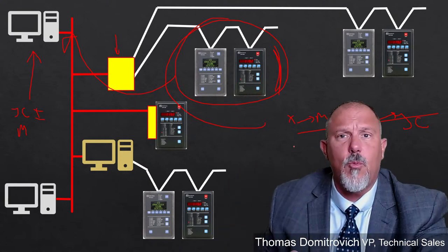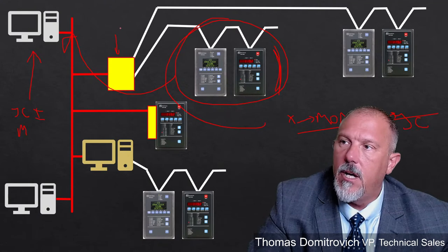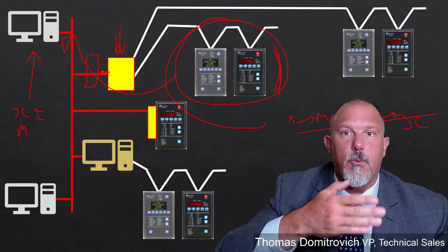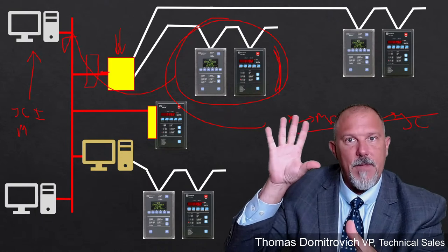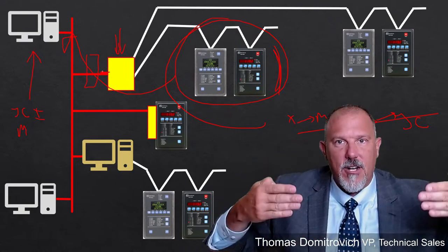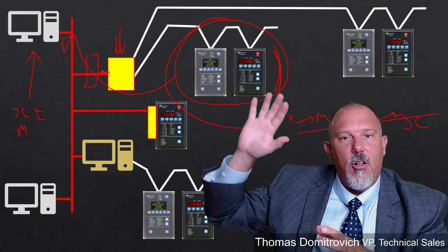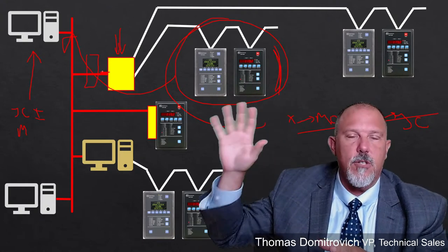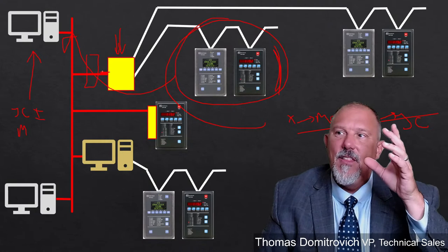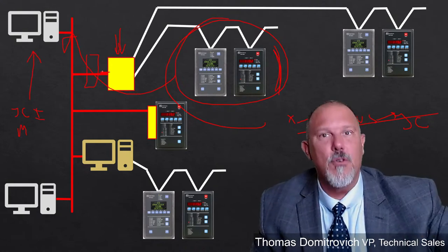I did one job that was Conitel 2020. I had a whole bunch of devices, and there was a computer that was here. I had another computer here, and in between I had an RS-232 network, and I had a card that had an octopus out, which went out, I think, to 9 different RS-232 channels. Both computers had these octopus cards, and I would connect all of those together. The one box took all of my metering information, which was from multiple manufacturers, and converted it over to a Modbus register going out through each port. And then the second computer took all those Modbus registers in, converted it to Conitel 2020, and put that out over to another system.